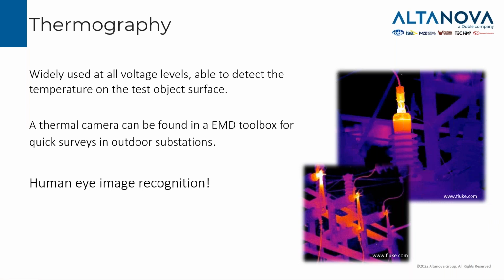The first method presented here is thermography. We put it here, even if it's not, let's say, typical for underground cables. It's something that is very popular in substations and can give us feedback as well on the cable terminations, which are present in the substation. So it's something that you can always find in an EMD toolbox, and it works with a very easy working principle, that is human eye image recognition. So it's quite applicable to everyone. There is no deep training or deep skills involved, and it's a quick thing that everybody can do with, let's say, limited effort.